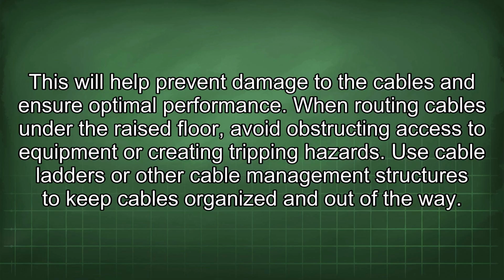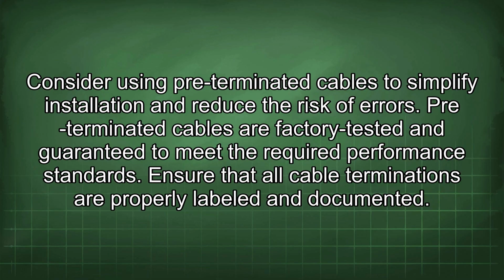When routing cables under the raised floor, avoid obstructing access to equipment or creating tripping hazards. Use cable ladders or other cable management structures to keep cables organized and out of the way. Consider using pre-terminated cables to simplify installation and reduce the risk of errors. Pre-terminated cables are factory tested and guaranteed to meet the required performance standards.